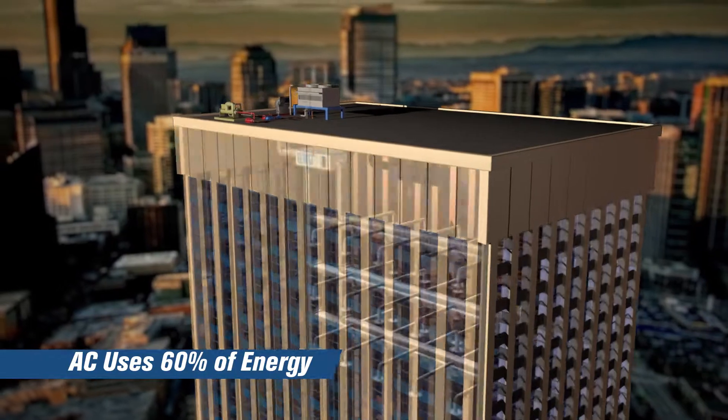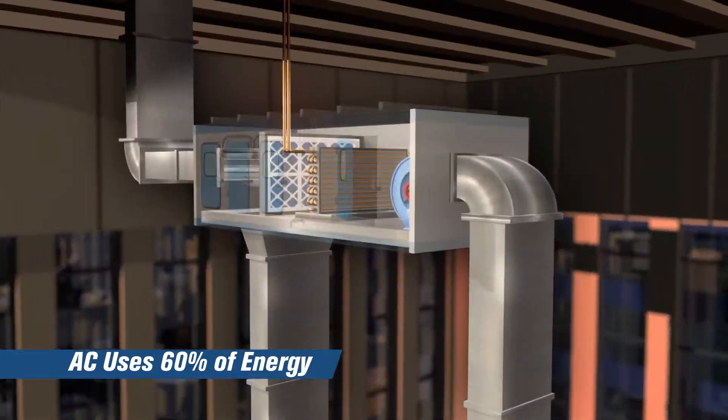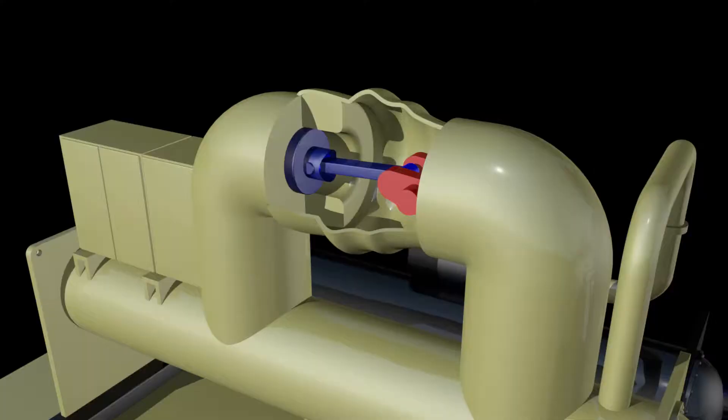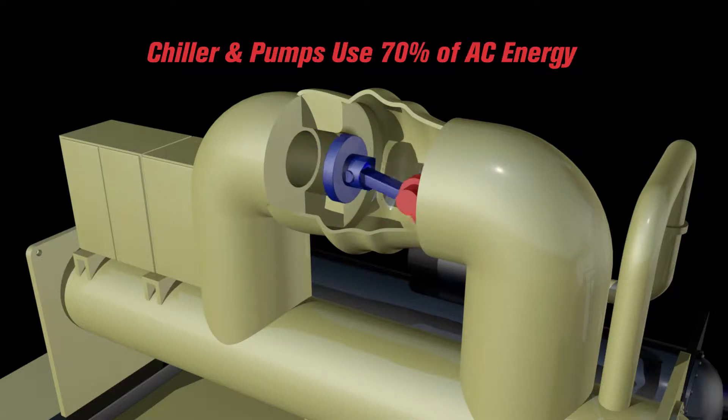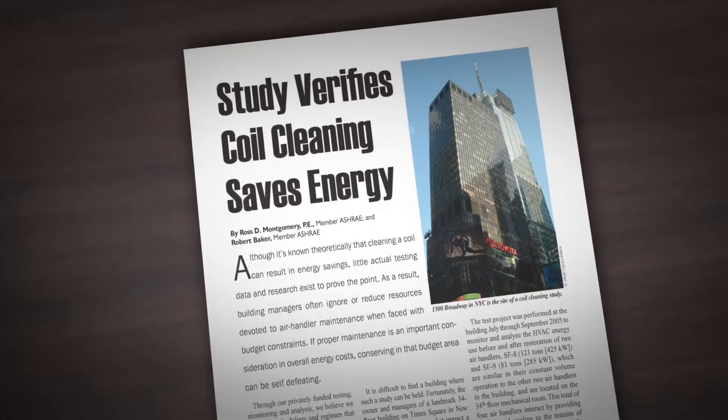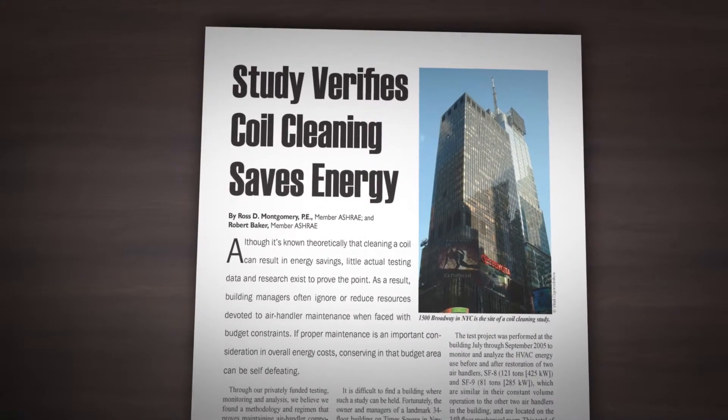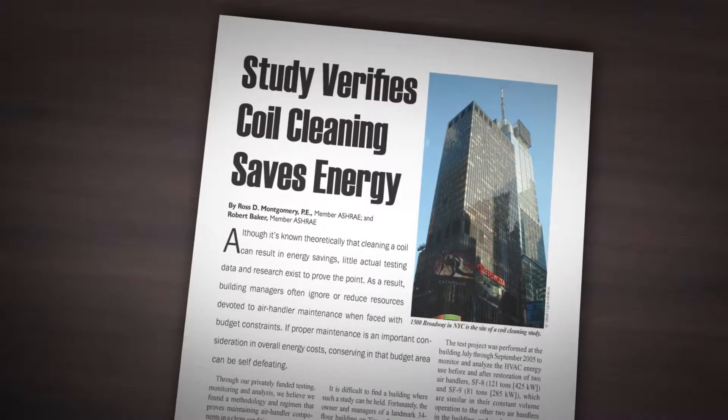In a typical office building, the AC system uses 60% of the building's energy, and of this, the chiller and pumps consume 70%. The 2006 ASHRAE published study estimated savings of 15 to 30% from clean coils.